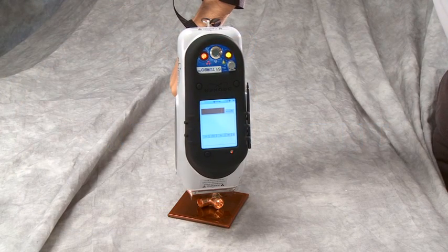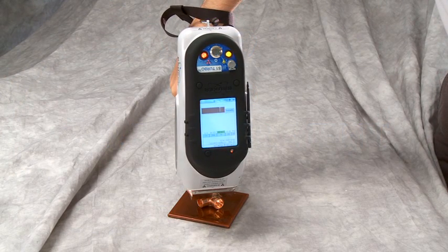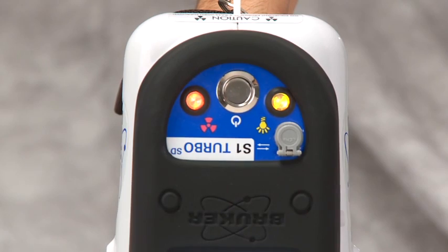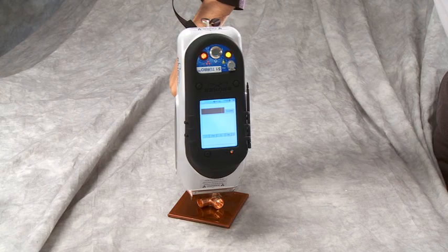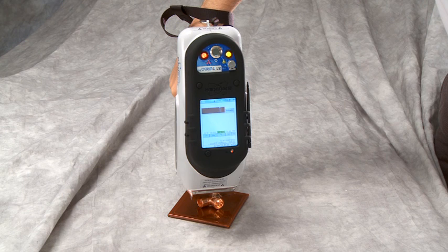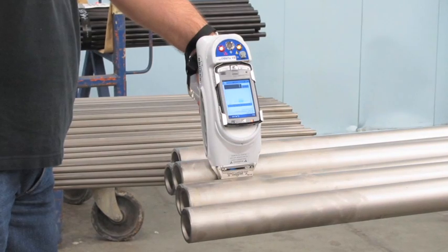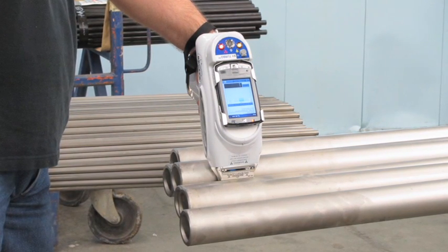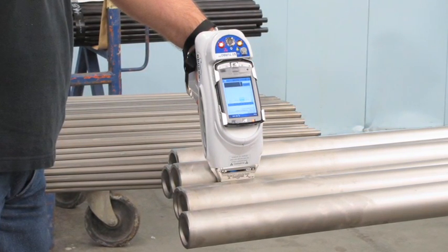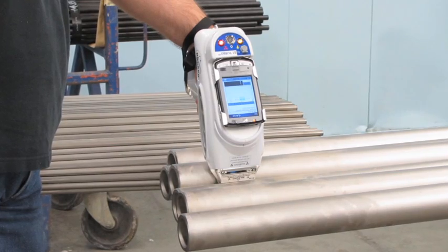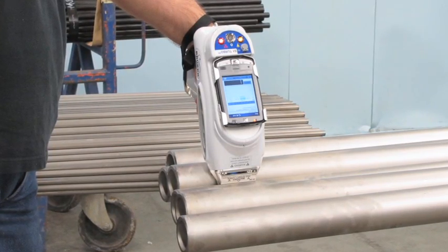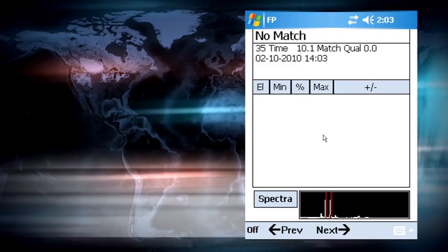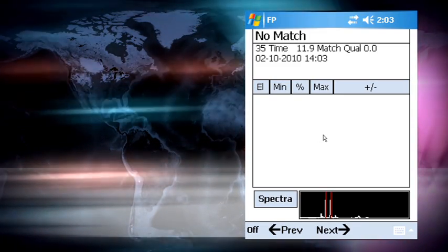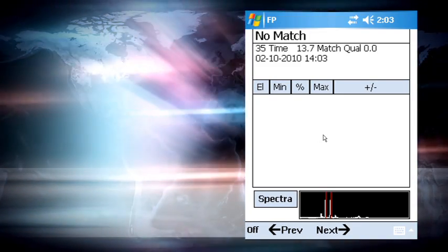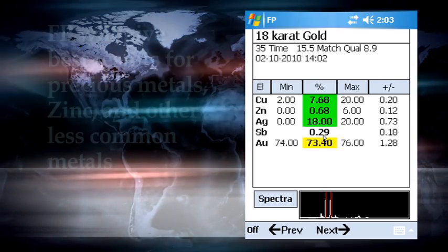Fundamental parameters analysis is the best technique to measure any sample which is truly unknown. If you are measuring a common alloy, such as steel, copper, or nickel alloy, it is probably within the boundaries of the empirical calibration. However, unusual alloys fall outside of the calibration boundaries, and the empirical analysis may be compromised. Fundamental parameters analysis may not be as accurate as the empirical analysis, but it will provide much more accurate results for samples well outside the boundaries of the empirical calibration.